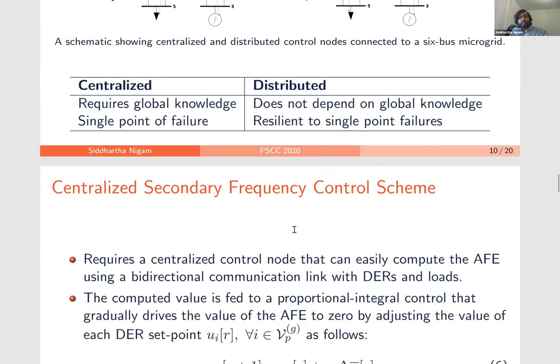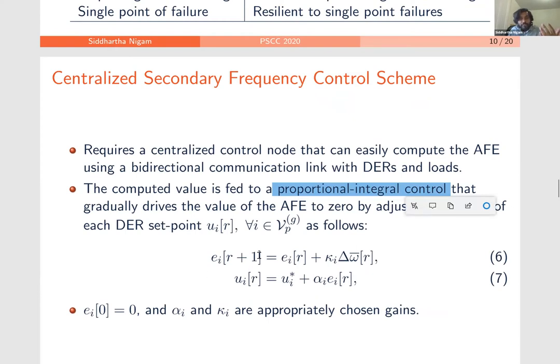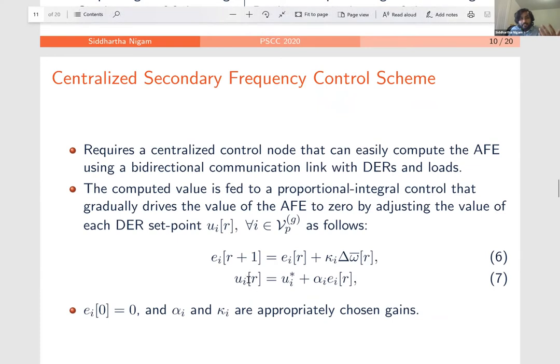In the centralized frequency control scheme, the centralized node polls for the set points, computes the frequency error, and passes it through a proportional-integral PI-based control. From equations six and seven — the details are in the paper — the individual set points of the DERs are updated. As perturbations keep happening, the hope is that the frequency error goes to zero as long as the gains are chosen appropriately.